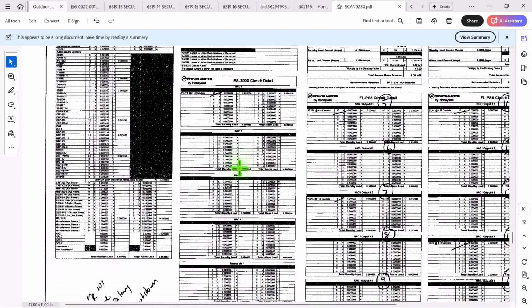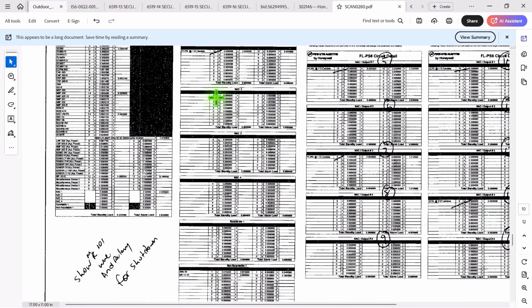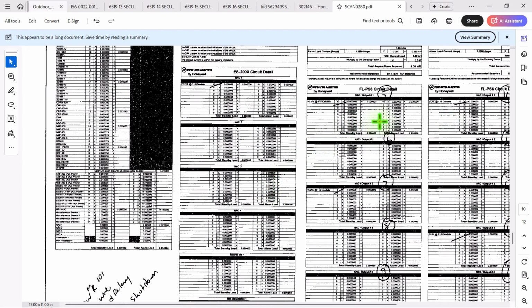So these are the NAC outputs off the main fire alarm control panel, serving these 10 devices in that one area. I couldn't put anything else on this panel because it was too much power, so I had to add these 2 booster panels.